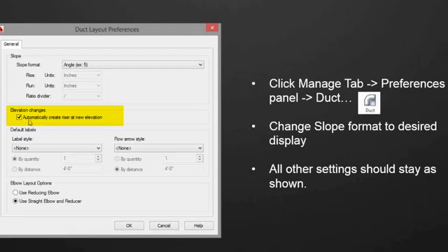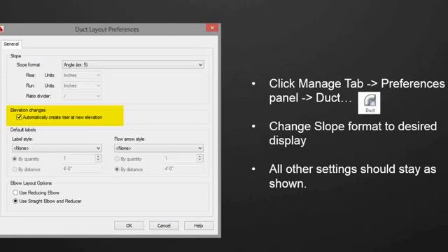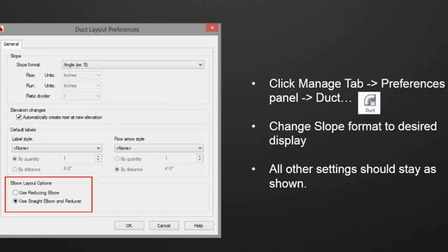Elevation changes. I have automatically create a riser at a new elevation checked, so as I'm going along and I'm drawing duct at the command line, I can just type in E for elevation during the duct add command, and then type in an elevation immediately after that. And the duct will rise or drop down to that elevation, put in your elbow, and do everything else that's needed.